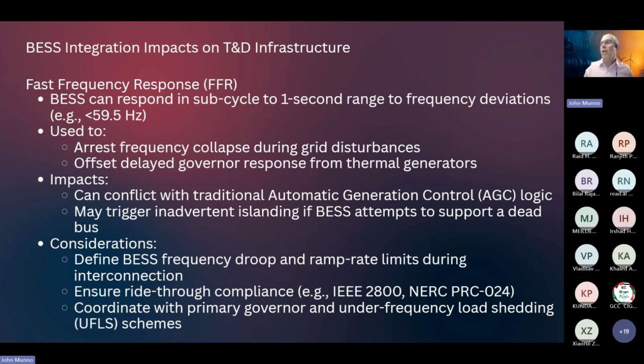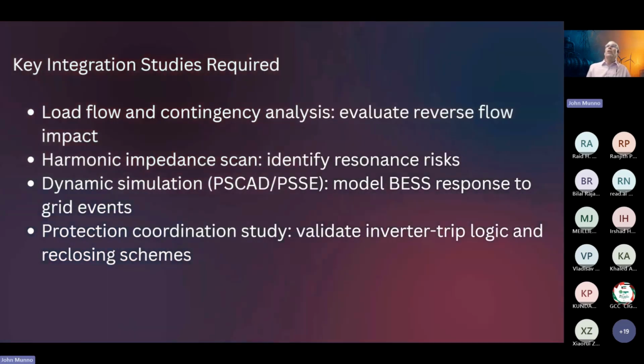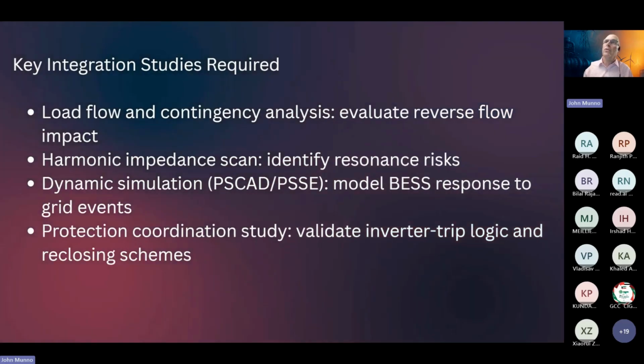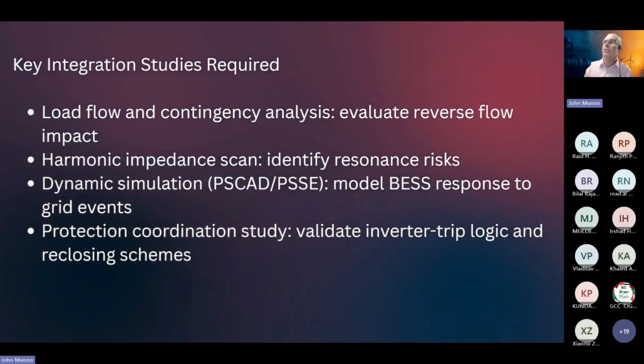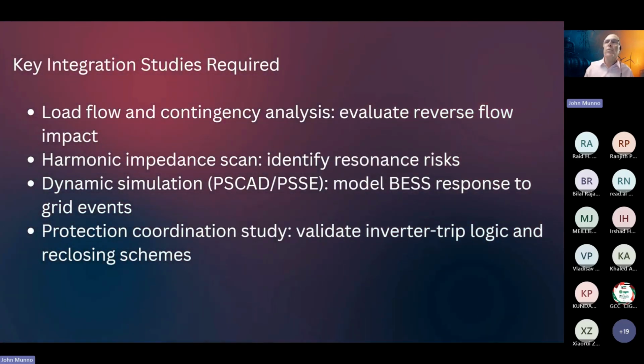So the key integration studies required are the load flow and contingency analysis, evaluate reverse flow impact, harmonic impedance scan, identify resonance risks, dynamic simulation, model BESS response to grid events, protection coordination study, validate inverter trip logic and reclosing schemes.